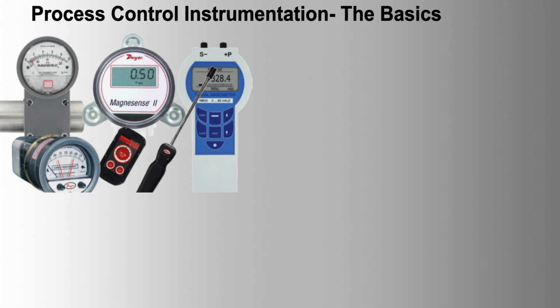4. Installation requirements. Follow manufacturer guidelines for straight pipe lengths upstream and downstream to ensure accurate measurements. 5. Material compatibility. Select materials that can withstand the process fluids to prevent corrosion and fouling. 6. Calibration and maintenance. Regular calibration and maintenance are necessary to ensure the accuracy and longevity of flow meters. 7. Hazardous area certification. Ensure flow meters are certified for use in explosive environments.